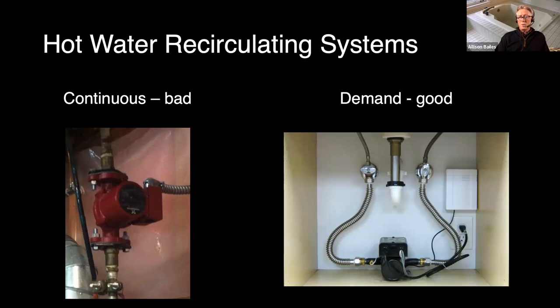The better way to do this is with a demand recirculation system, where you put a pump at the farthest fixture, or a fixture that's far away anyway, and you can push a button or have it motion activated so that it circulates the water. It'll bring the hot water to the fixture and push it back into the cold water pipe, or you can put in a return line if you want.